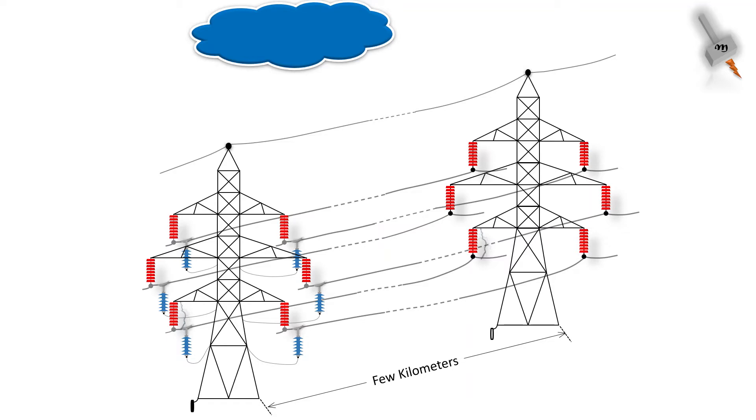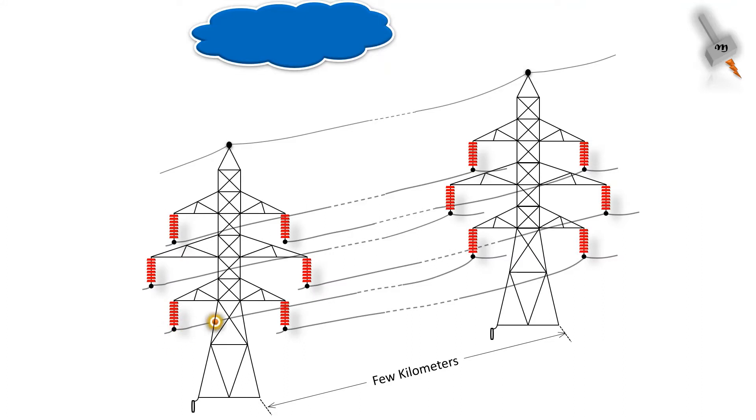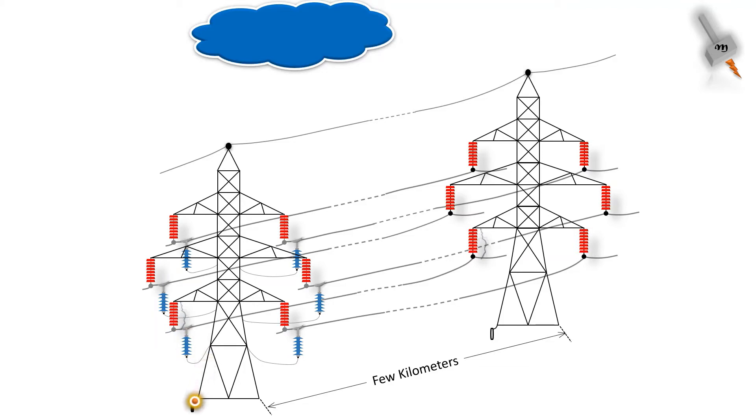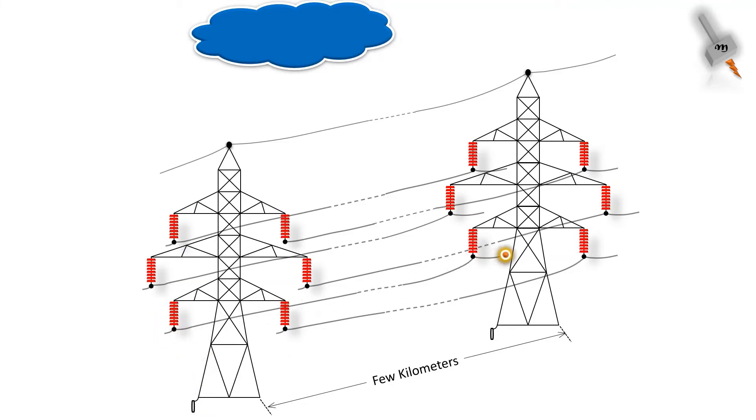This flashover will induce a surge in the power lines. It can happen that the same tower where the flashover happened, a lightning arrester will be installed. Then in that case, the surge will be grounded quickly. If there are no lightning arrester installed in the tower, the surge will continue to travel over the power lines. If it finds a tower with lightning arrester, it will be grounded. Else, it will go to the substation where the dead front arrestor will ground it.